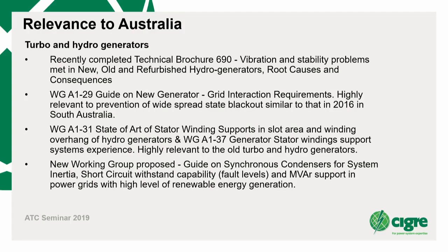Working group 37 covers stator winding support system experience. Don't let them anywhere near 100 hertz vibration — they shake themselves to pieces. I've seen some of them, and once you see this brown fretting dust around the end winding, that's when you're going to have problems. We are working to prevent those things. As I mentioned earlier, with old machines, these things happen quite regularly.